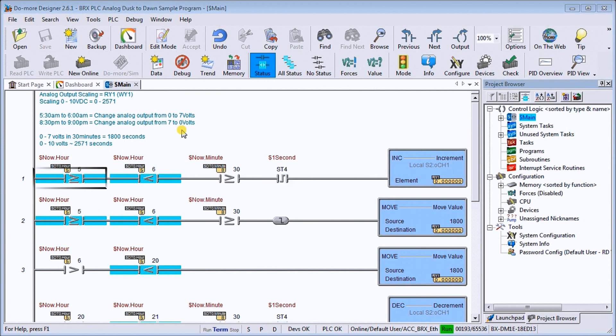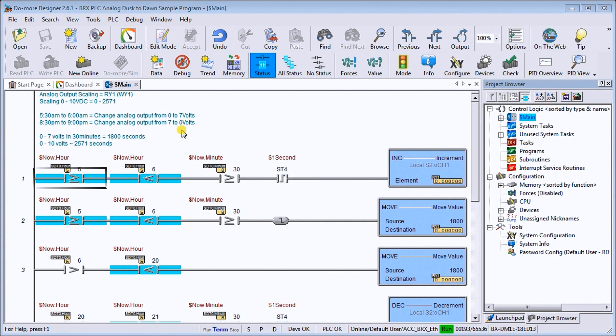I was recently asked about such a program. Every day they wanted the lights to go off at 10 p.m. and come back on at 6 a.m. And at 9:30 p.m., the lights would be on at 70% or about 7 volts of the 0 to 10 volts analog output signal.